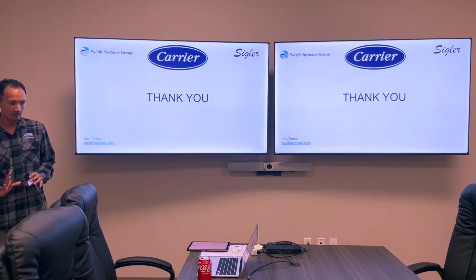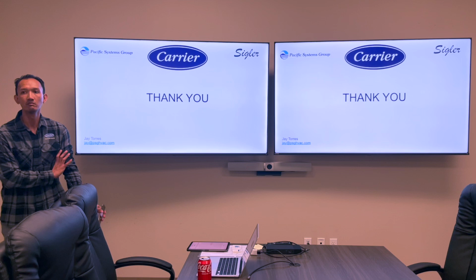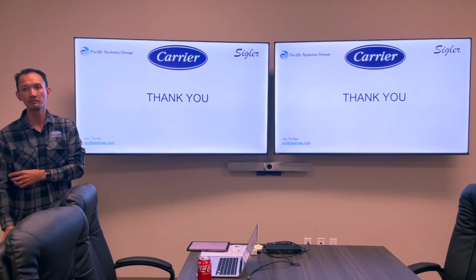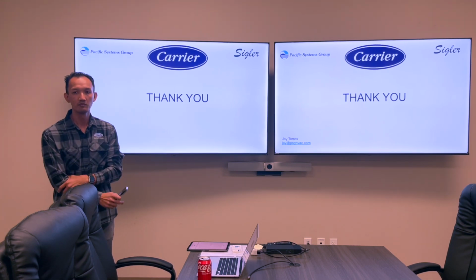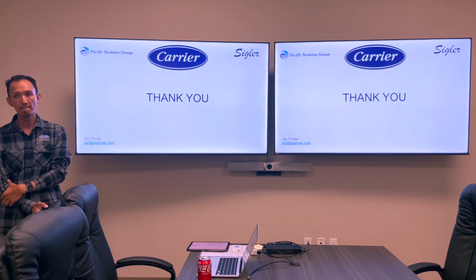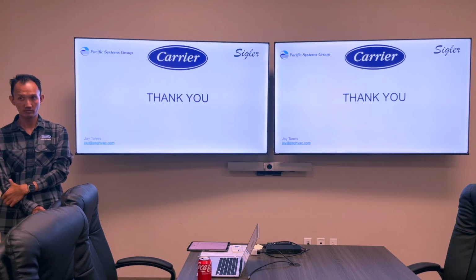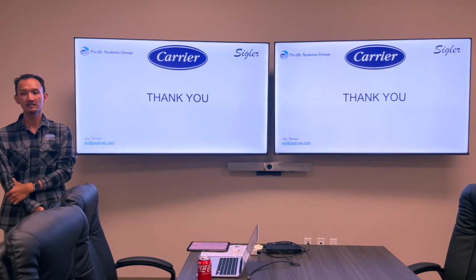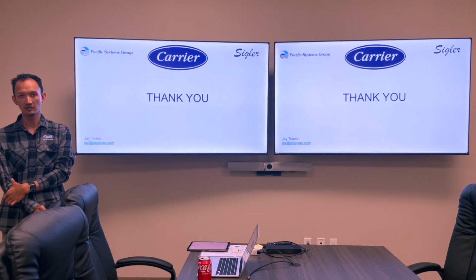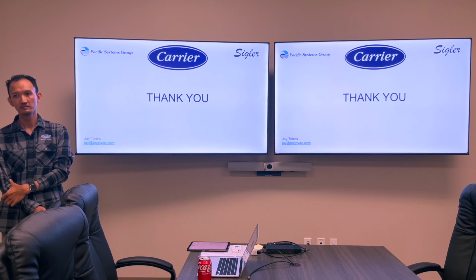Do we have any questions that have come up during this time? For example, that 2,000 square feet office, we're allowed to have 22 pounds of refrigerant, right? Yes. Then we have 10.5, almost. So we comply with ASHRAE 15. Yes. Let's say this 2,000 square feet is a restaurant, and we need like 15 tons, and we end up with like 30 pounds in our actual system. We don't comply with ASHRAE 15, right? Will the SV box solve that issue?